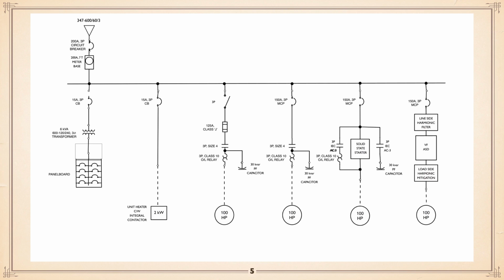Time delay. And below that we have our starter, and splitting from the starter we're showing where we've got a power factor correction capacitor. And also noting we have class 10 overloads, which we discussed earlier, because they're fairly quick trip. And for most centrifugal pumps, just great. The next one is showing the same thing, but only with a circuit breaker, which I would prefer, as you know, to the disconnect fused switch.